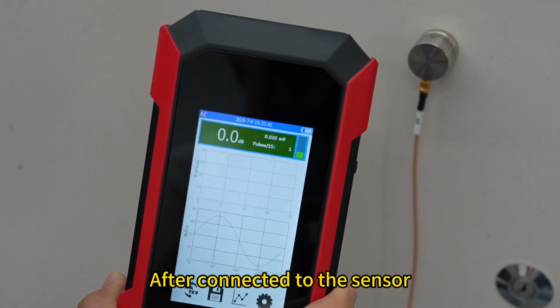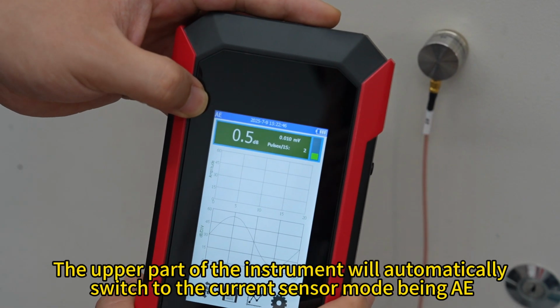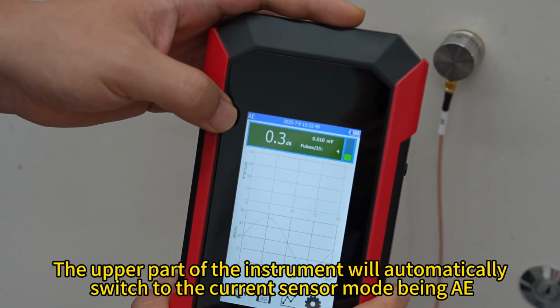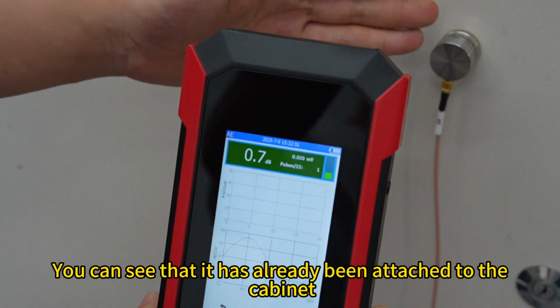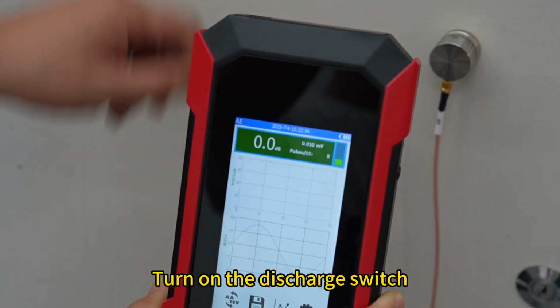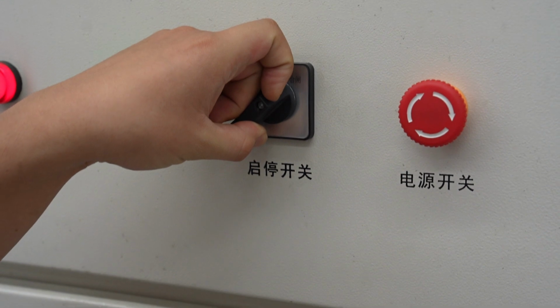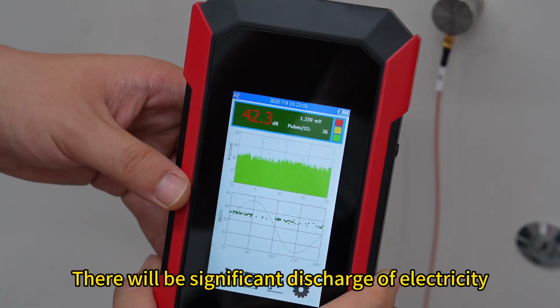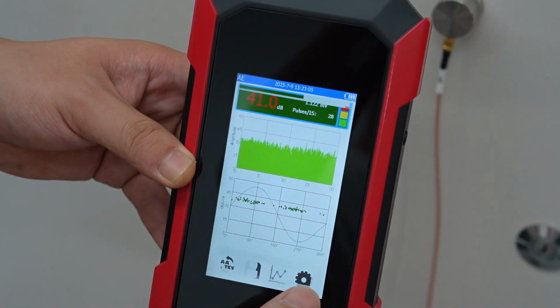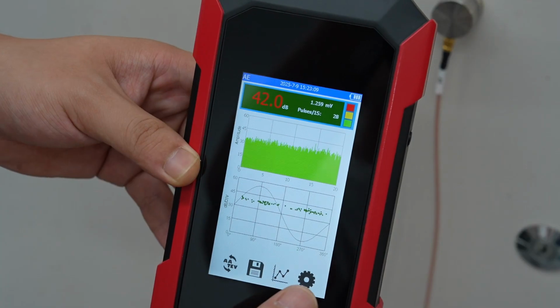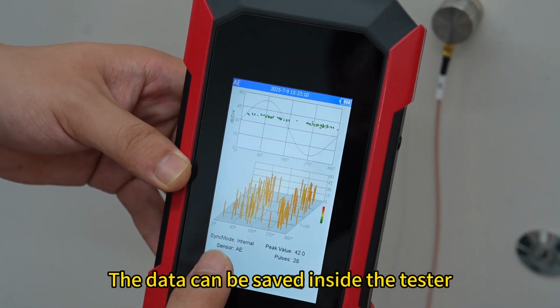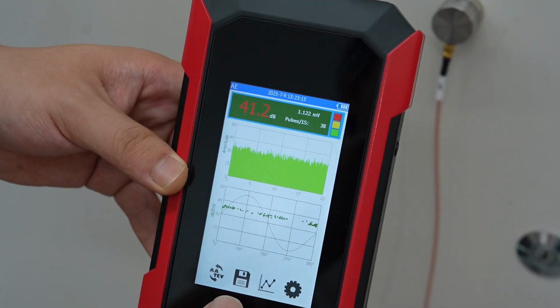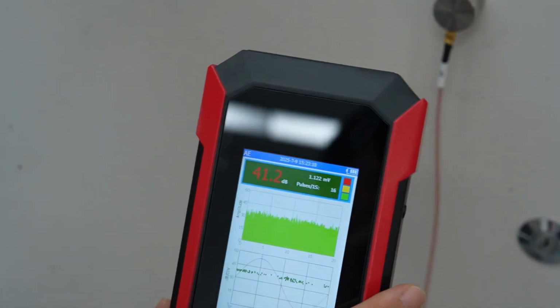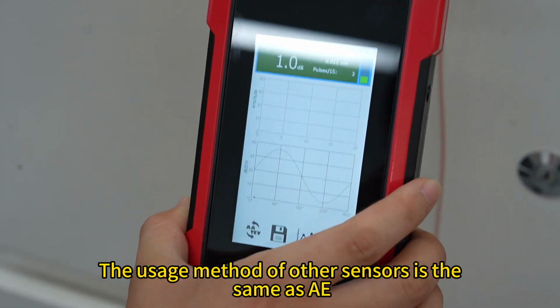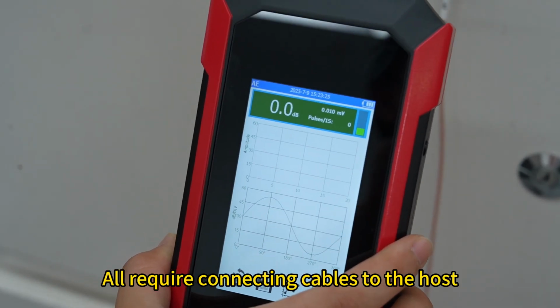After connecting to the sensor, the upper part of the instrument will automatically switch to the current sensor mode, being AE. You can see that it has already been attached to the cabinet. Turn on the discharge switch. There will be significant discharge. The data can be saved inside the tester. Stop. The usage method of the other sensors is the same as AE. All require connecting cables to the host.